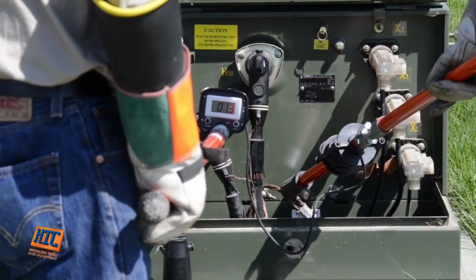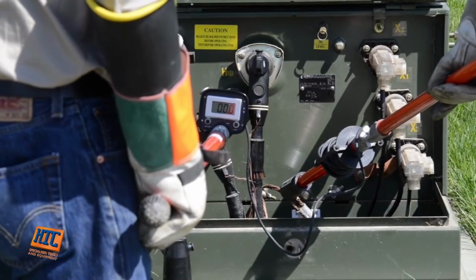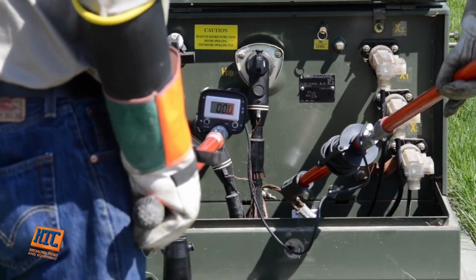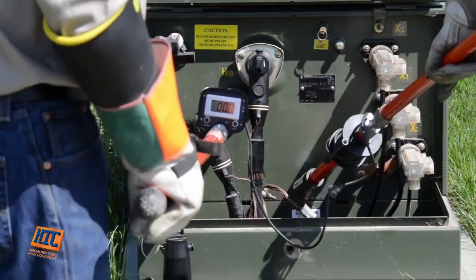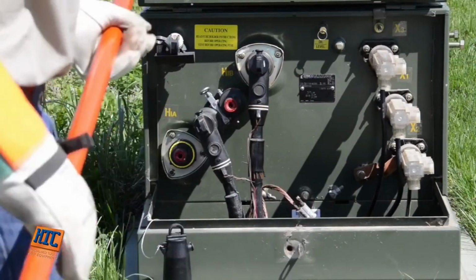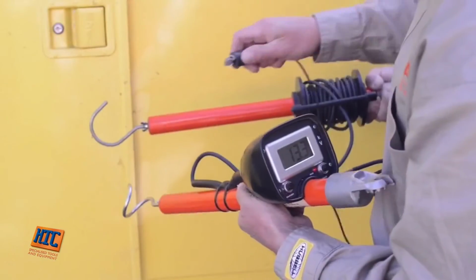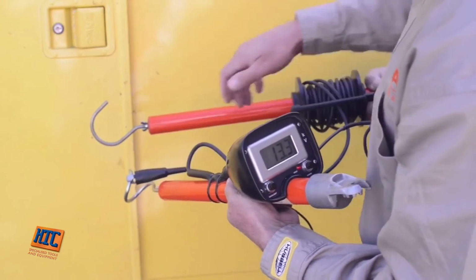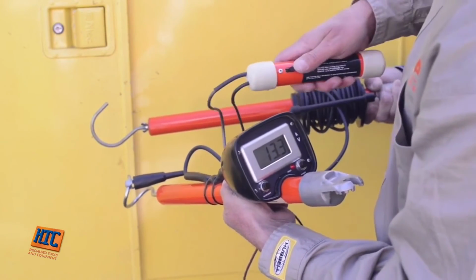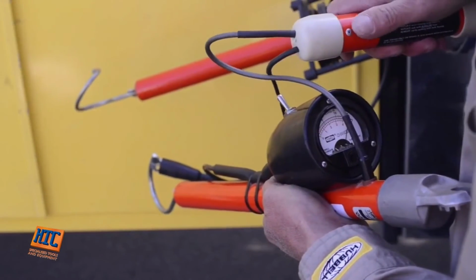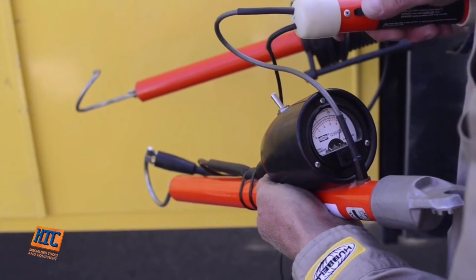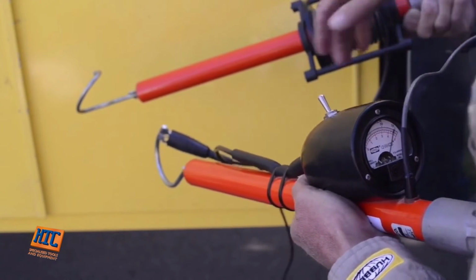The follow-up procedure when high-pot testing with either the analog or digital phasing tester is to discharge the cable that was tested, using the tester on the feed-through and touching the reel probe to the system ground. Finally, as before, either phasing tester must be checked to verify it is still fully functional, again using the voltmeter tester for phasing testers listed in the instruction manual.